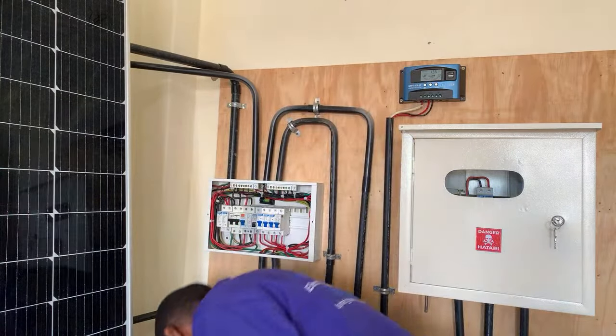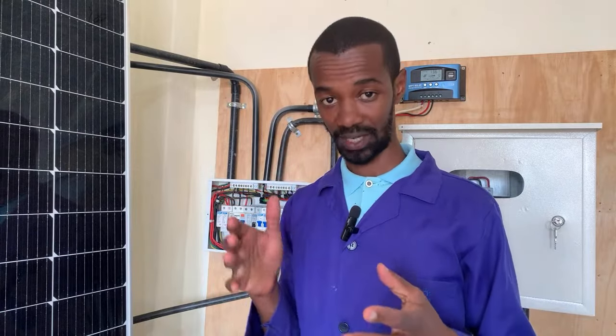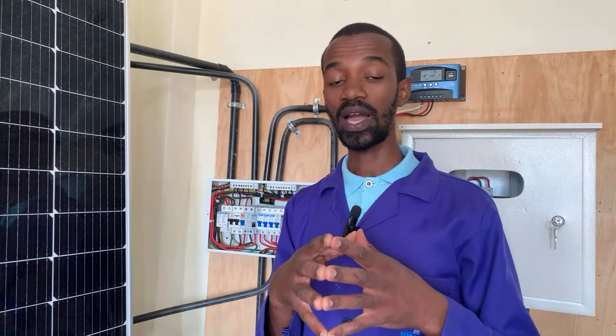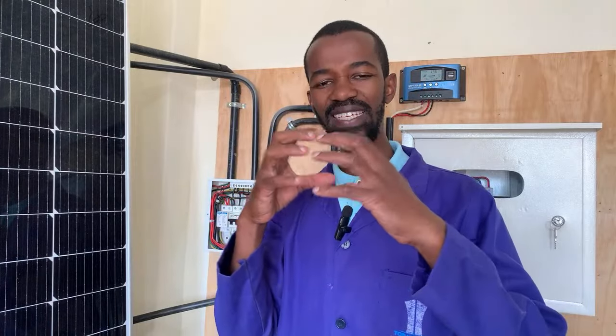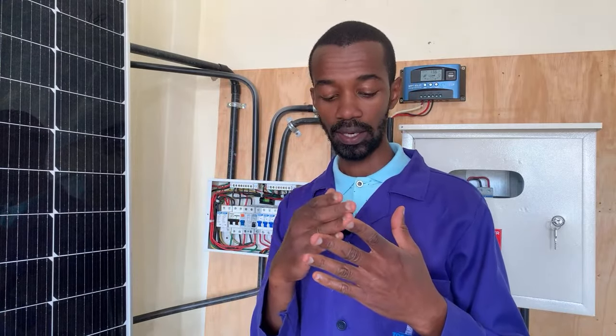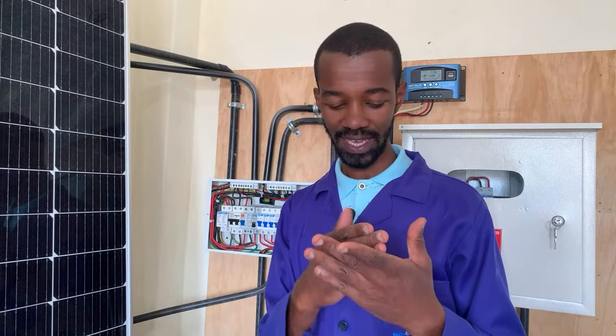As much as it's a single domestic wiring, you might have several lighting circuits which are dedicated to different MCBs. So it doesn't mean that just because it is a home, let's say a single phase installation, or we have a 3-bedroom or a 4-bedroom or a 5-bedroom, that you take all those lighting points and have one wire supplying the entire lighting points. No, that is not a good wiring system. You need to have, let's say, several bedrooms dedicated to one MCB. And then you can have one MCB dedicated to, let's say, a corridor and stairs. Okay, so those are two.